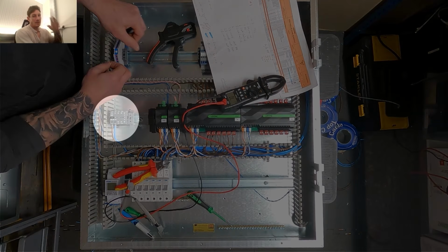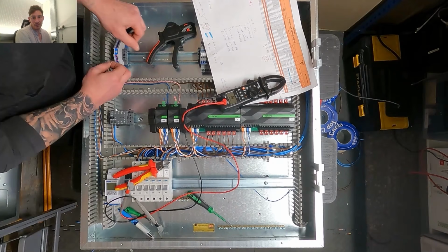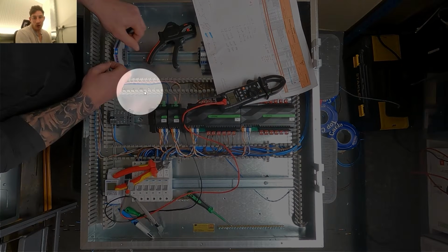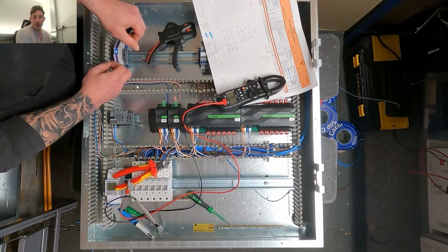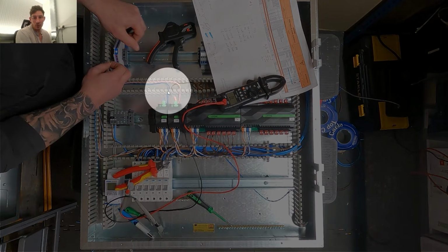That's contacting, opening and closing, not necessarily on-off like that, but I'm just mitigating any risk. That's got 13 amps running on these cables, which are going to be running in the same trunking, and you'll see how I segregate them in a bit to reduce that potential. You've got those cables running next to each other.